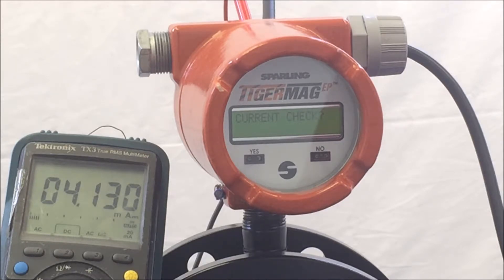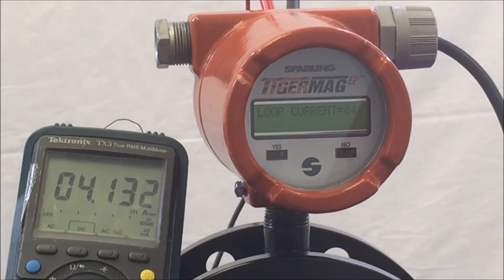The meter is forcing the 4 to 20mA output to advance to 4mA, which can be observed on the outputs. This requires a meter or a reference for the 4 to 20mA output. Hit No and the loop will advance.